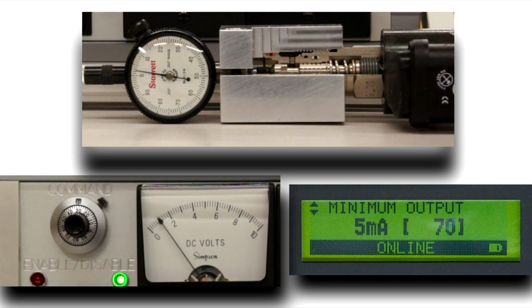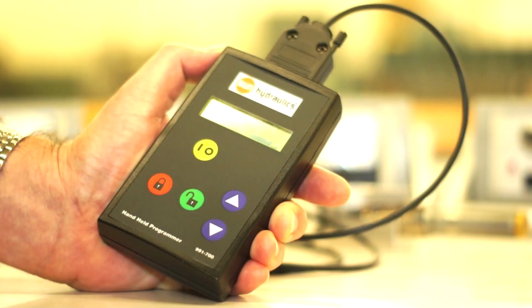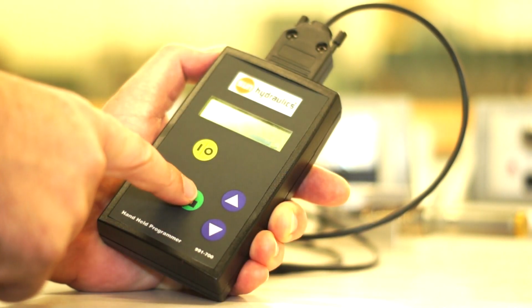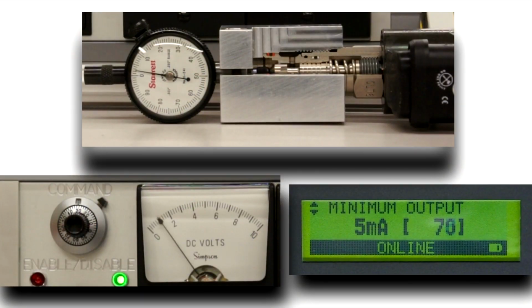To remove this minimum input deadband, we can capture the value and use it as the new minimum. To do this, hit the green unlock button to capture, and then hit it a second time to lock the value in. It will appear in the right-hand side of the display in parentheses. Or you can hit the unlock button once and use the up and down arrows to adjust the values, and then hit the lock button to save it. Now we have the greatest input control resolution.